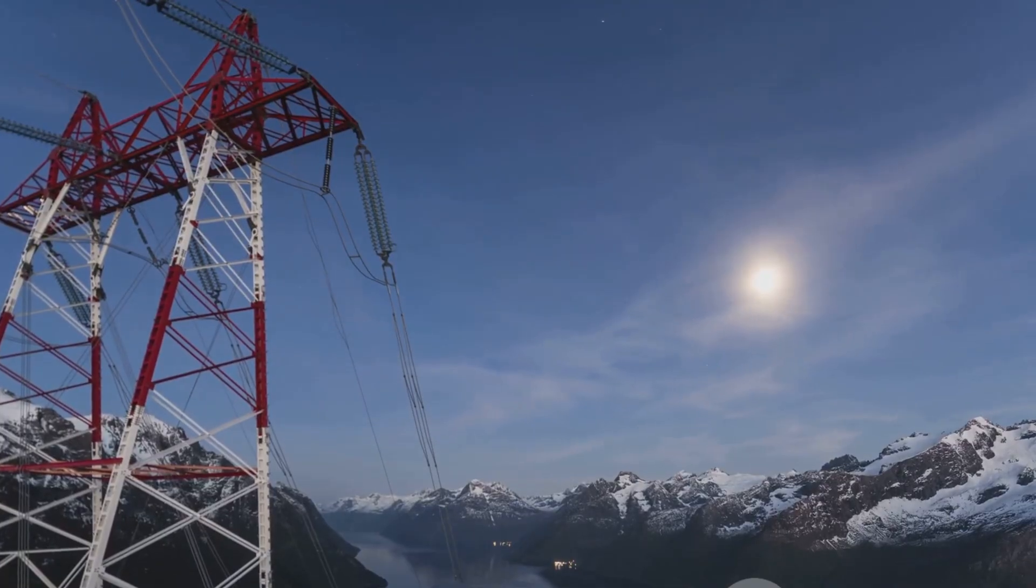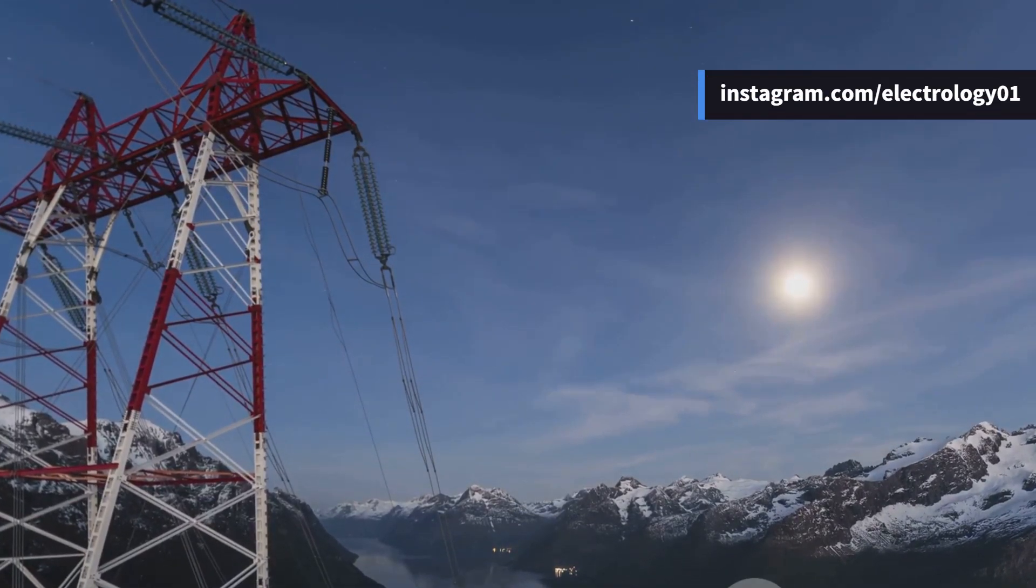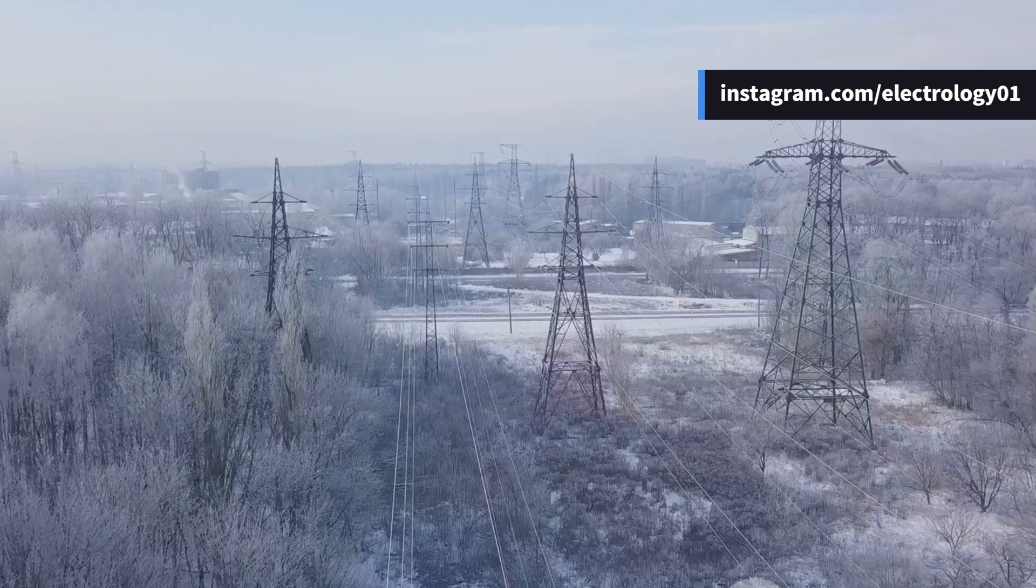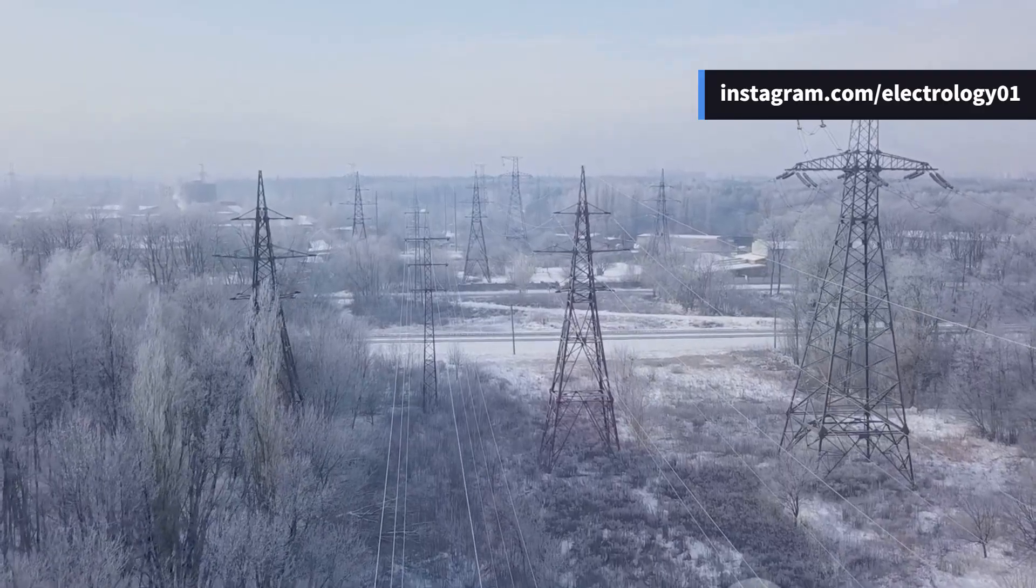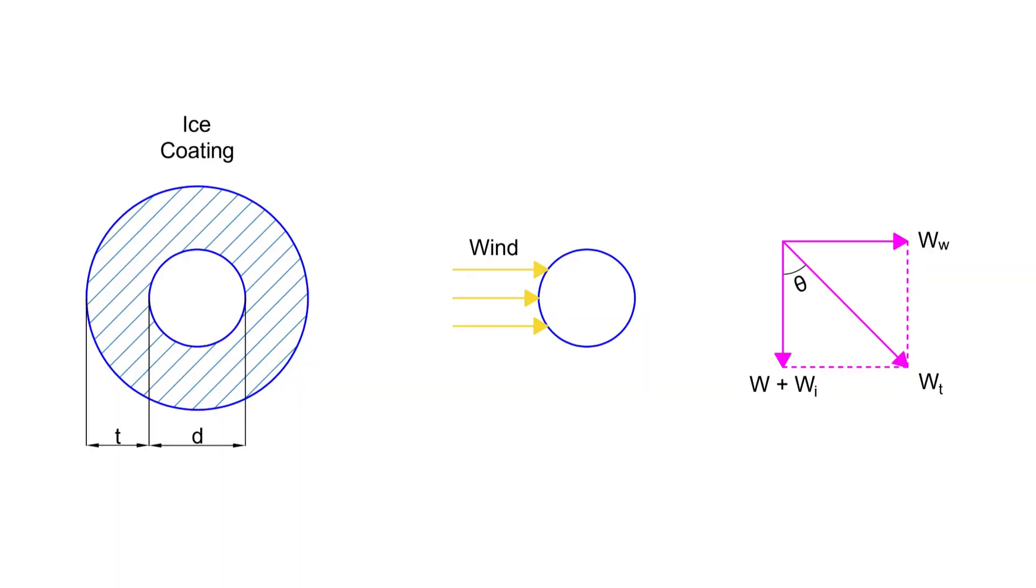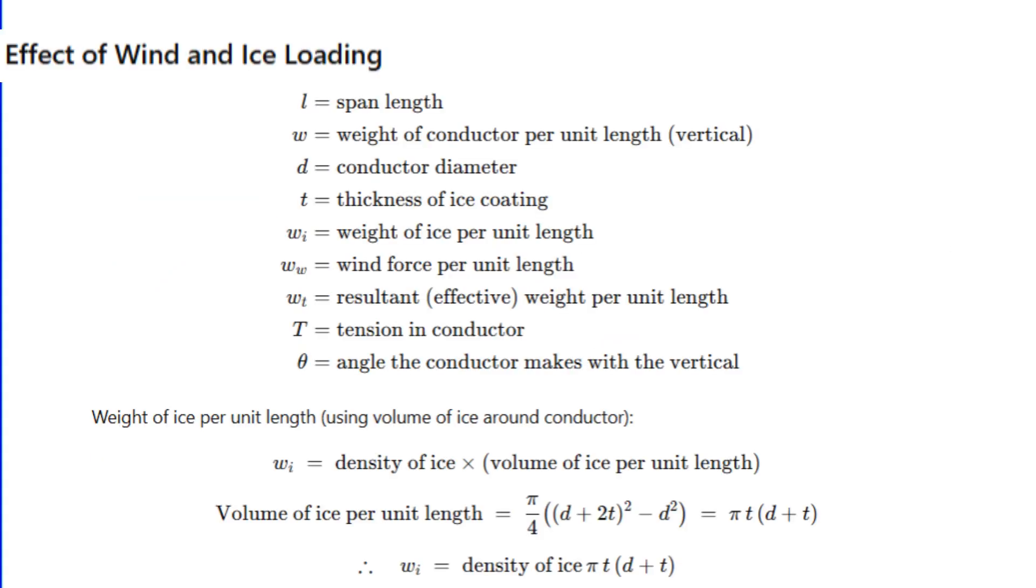Now let's make it even more realistic. In practice, conductors don't just carry their own weight—they often get coated with ice in cold areas, and at the same time wind pressure acts horizontally. So the total force is the vector sum of vertical and horizontal forces. The weight of conductor per meter is w, the weight of ice per meter is wᵢ, which equals density of ice multiplied by π·t·(d + t), where d is conductor diameter and t is ice thickness.